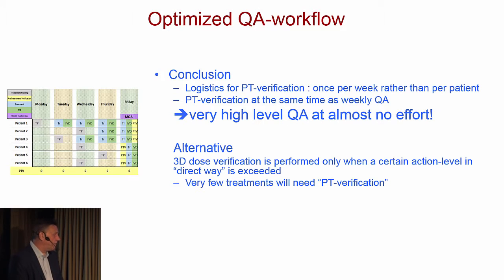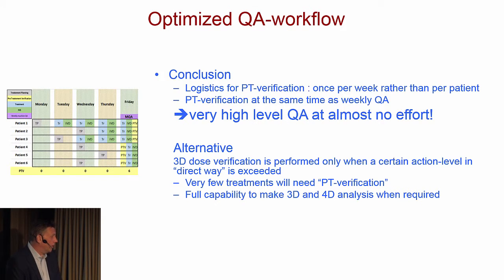In that case, very few treatments will need pre-treatment verification. Full capability to make 3D and 4D analysis when required. So, for example, if you've been treating a patient for a couple of weeks and then suddenly you have a discrepancy which exceeds your tolerances or action levels, then you perform your pre-treatment verification and you calibrate the Delta4 Discover.